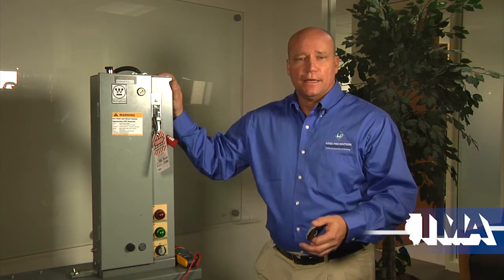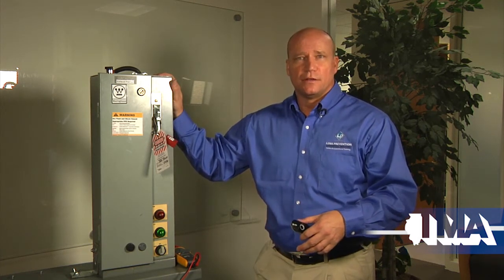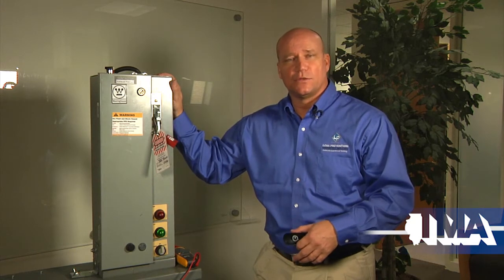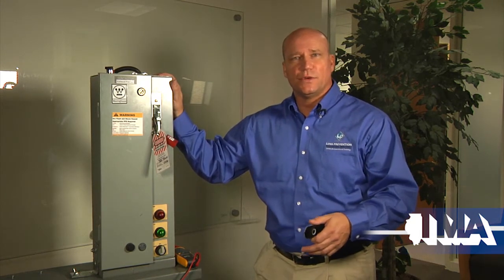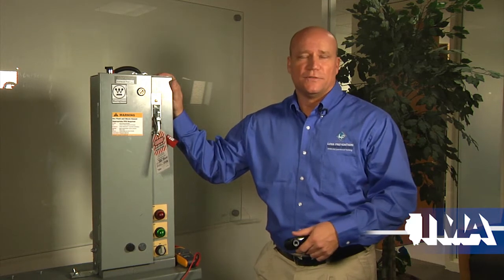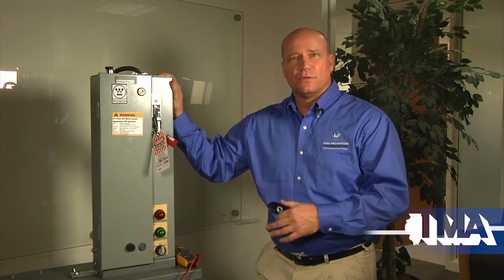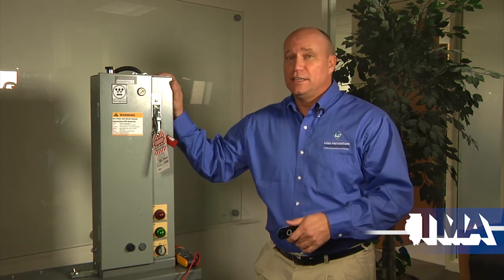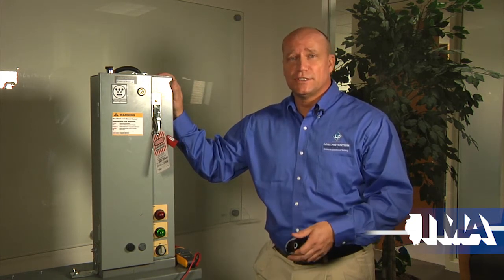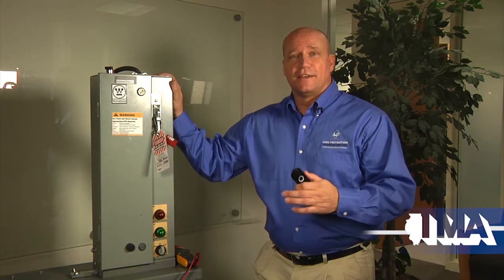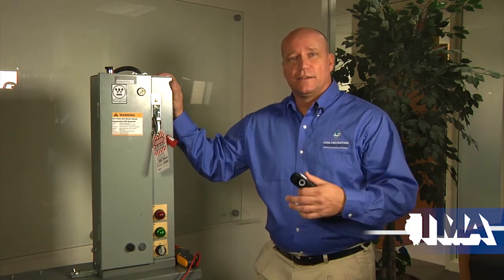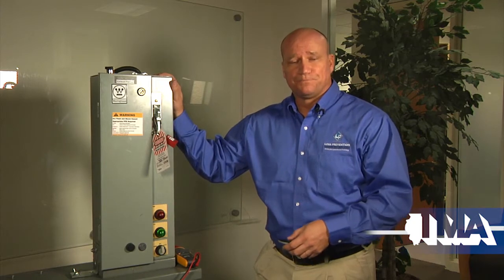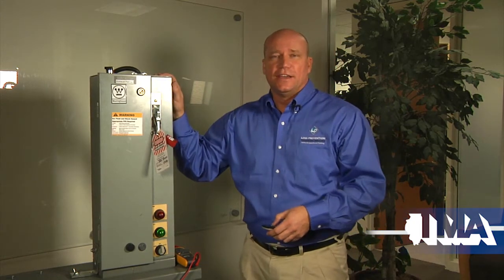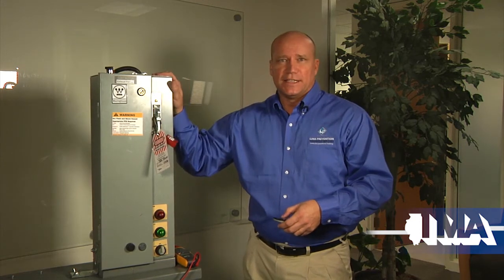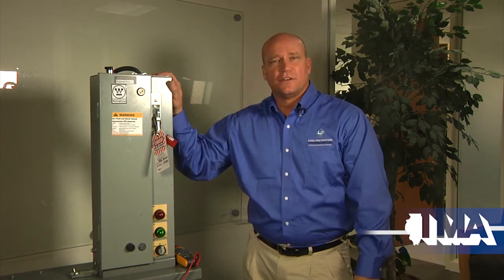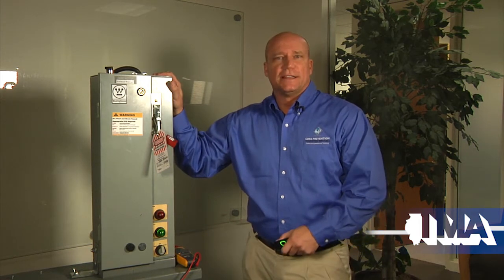People are human. If the person who's operating the switch, unfortunately, maybe they had a bad day, they got the wrong circuit. They should have opened circuit breaker number 3 on the panel board. Instead, they got circuit breaker number 5. It was a mistake, which would be caught when you do a live dead live. Other things that I've seen is mislabeling, particularly on new installations. And also circuits that have been installed incorrectly, meaning that the power source is connected to the wrong circuit breaker. So those are some of the possibilities that you have to be aware of when you're doing something as simple as a single source verification. And so we'll talk about that.